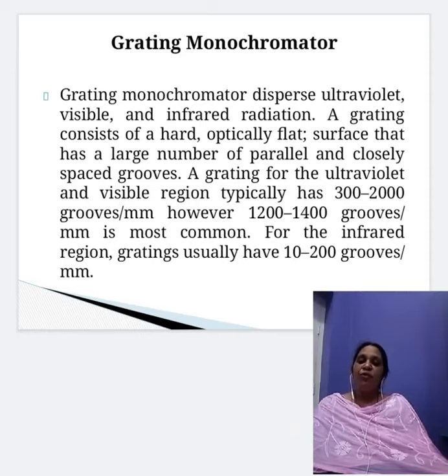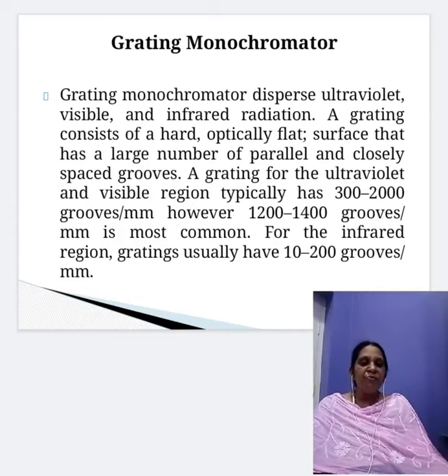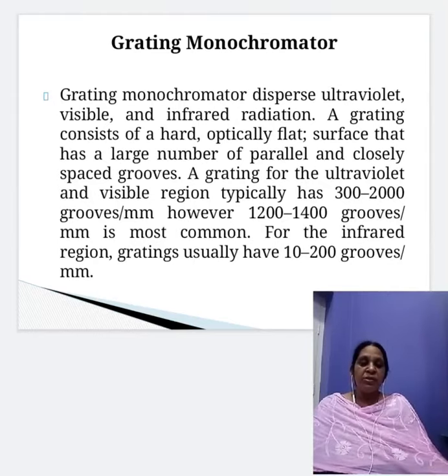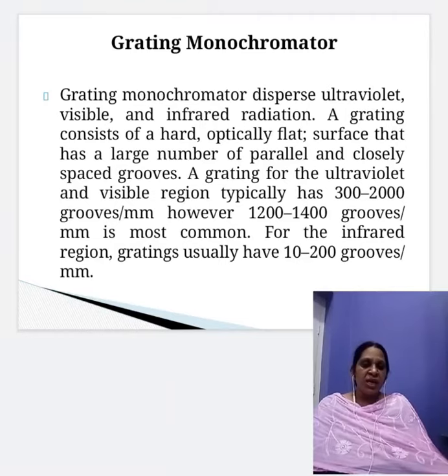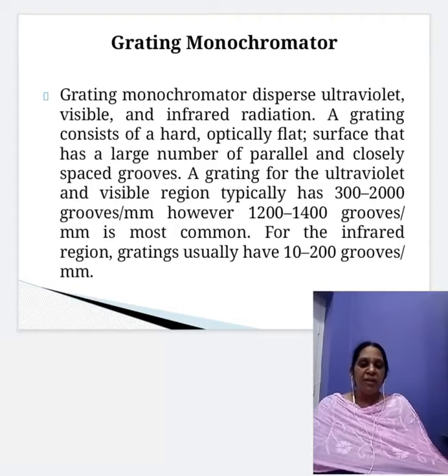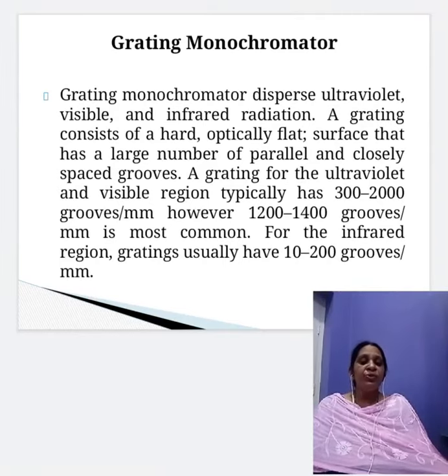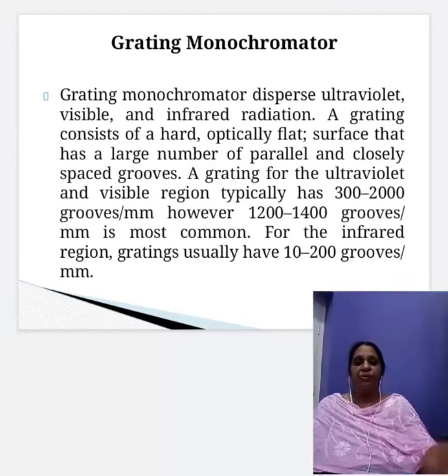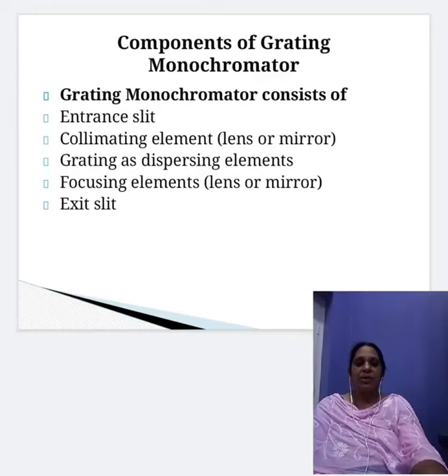A grating for the ultraviolet and visible region typically has 300 to 2000 grooves per mm. However, 1200 to 1400 grooves per mm is most common. For the infrared region, gratings usually have 10 to 200 grooves per mm — a very much smaller number.